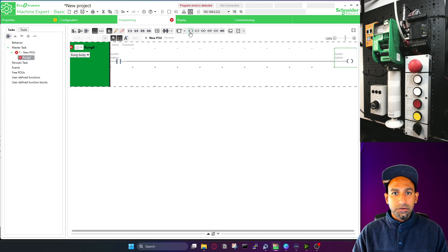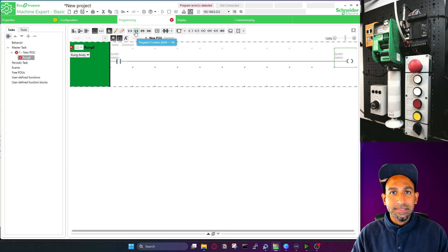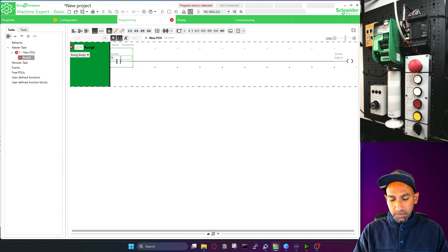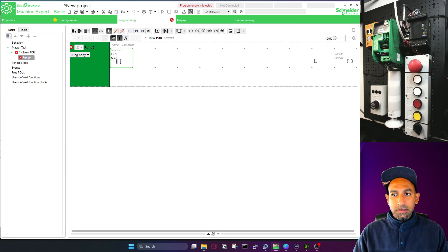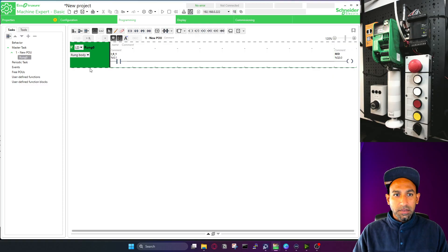If you take your mouse over here you can see some coil, and here we see negative coil — I will come to that. So here you have NO contact and there you have negated contact, also called NC contact. For this NO contact you can write the address — I write I0.1 and here I write Q0.0. That's how you add a rung.